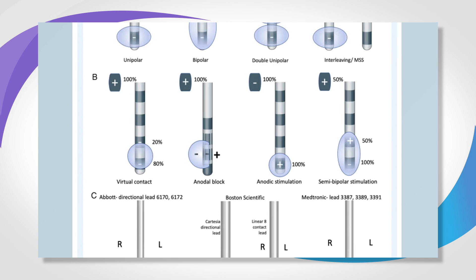Next to that is called the anodal block. Here there are two negative contacts together, so that is where the stimulation is coming from. And the third contact on that segment is a positive, or an anode.